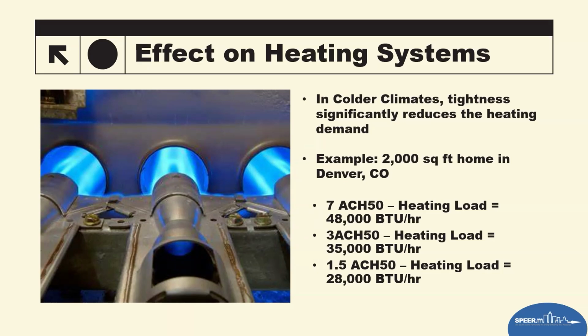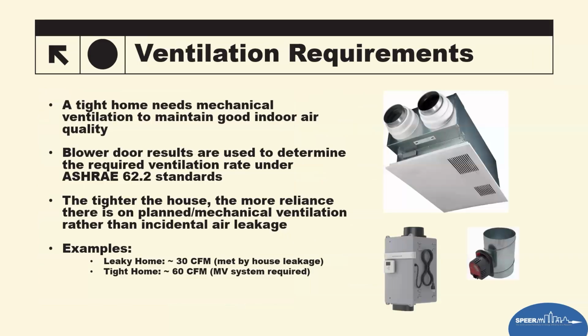I know back when my house was built in the 90s, and you talk to HVAC guys that used to do work back then, their biggest thing was, well, here's how we do it. We oversize the system by half a ton and we undersize the ductwork. That's how they always did it, and it would meet in the middle to be efficient and effective to heat and cool the building. But all the ducts sound like jet engines, and eventually all the screws came loose from the vents because it was shaking itself loose, because the velocity of air picked up from the smaller ducts that were not properly sized. That's what we're trying to eliminate as well.